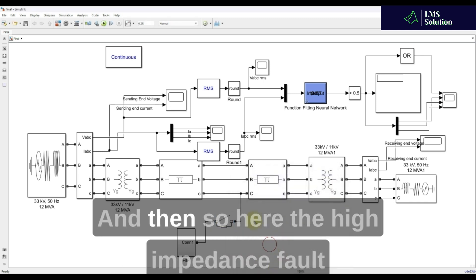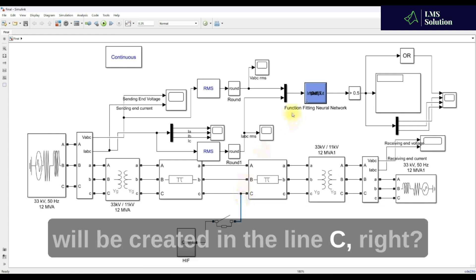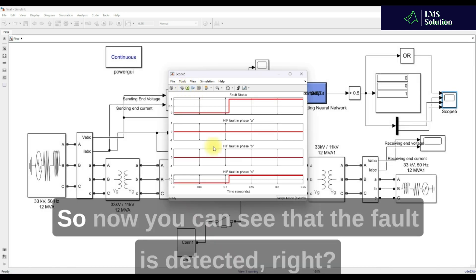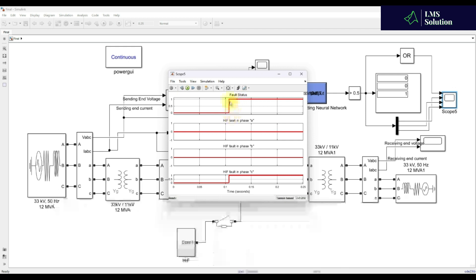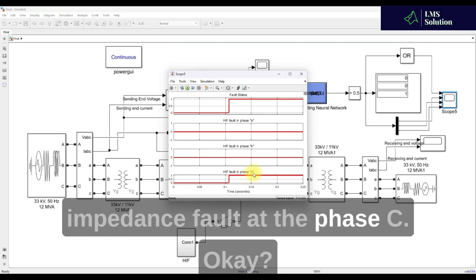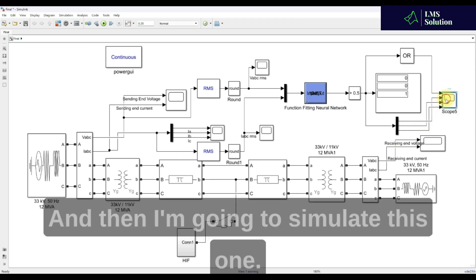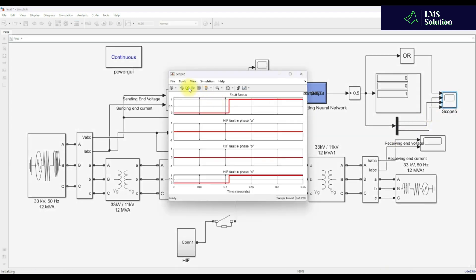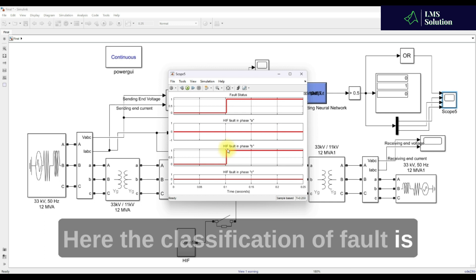Here I'm going to set the surface resistance to 70 ohms and create the high impedance fault on Line C. After simulating, you can see that the fault is detected and the classified fault is a high impedance fault at Phase C. Now I'm changing it to Phase B and simulating — the fault is detected and classified as a high impedance fault at Phase B.